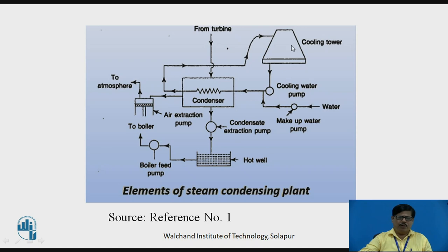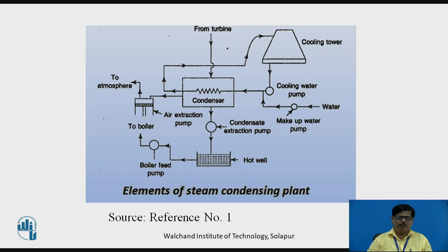If a large quantity of fresh water is not available for circulating inside the condenser, then we require an important device called a cooling tower. When the cooling water is circulated through the condenser tubes, it gets heated. This hot water is spread into the cooling tower, and due to the phenomenon of evaporation and direct contact between air and hot water, the cooling water gets cooled and is collected at the bottom of the cooling tower. This cooled water is then circulated through the condenser again using the cooling water pump. There are certain losses during evaporation, so makeup water is supplied with the help of a makeup water pump from a nearby source. These are the various elements of steam condensing plant and their function.